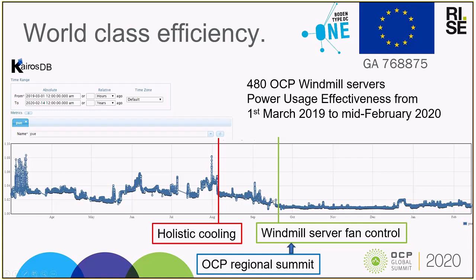And then we did another experiment where we actually took control of the Windmill server fans by putting a piece of hardware in. That was presented at the OCP Regional Summit in September in Amsterdam. From that point onwards, you can see that the PUE has been pretty much under control, irrespective of the workload that we've been operating from September onwards. We've been below 1.02 most of the time. Bearing in mind that we are running through the winter here, so we do have a slight advantage of not too hot weather outside.